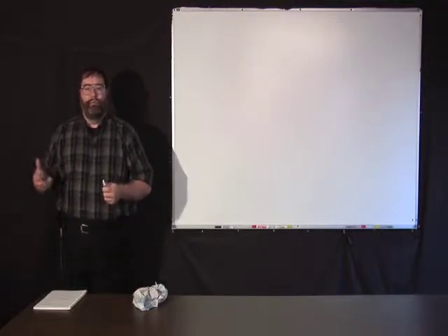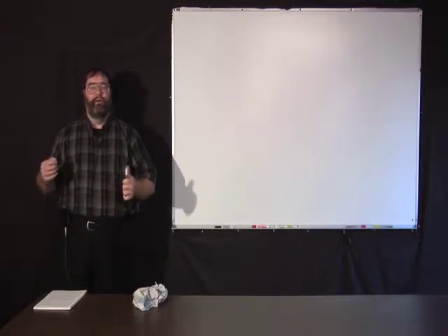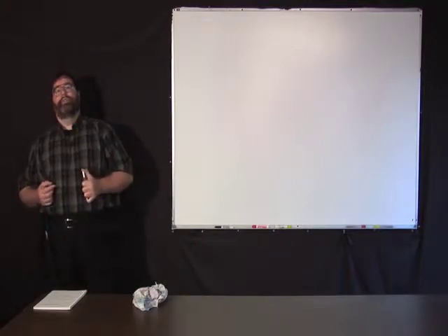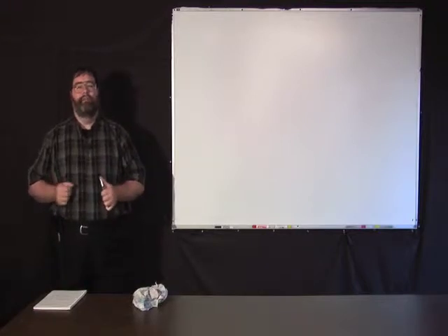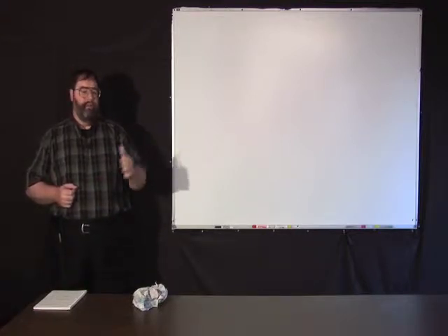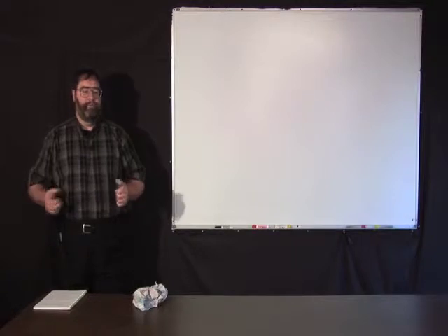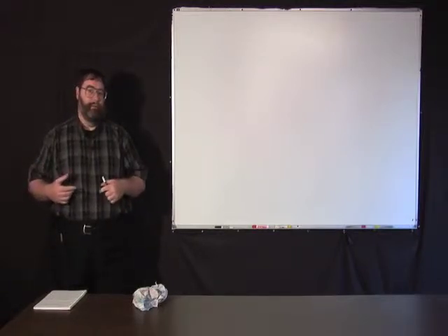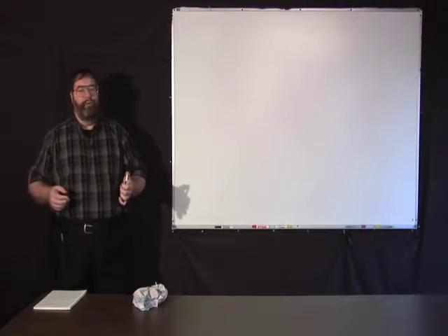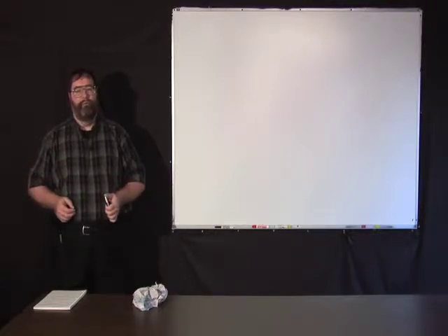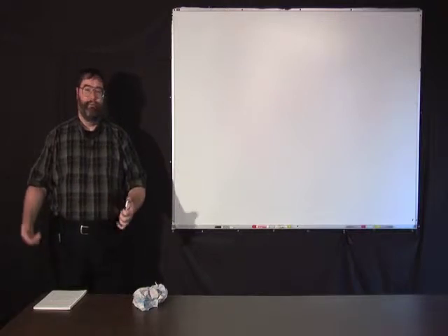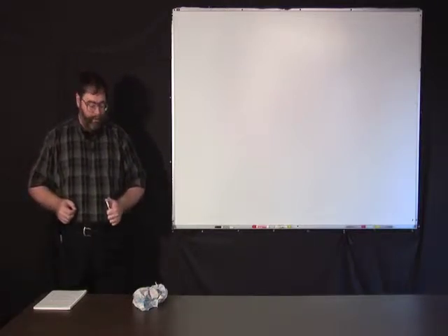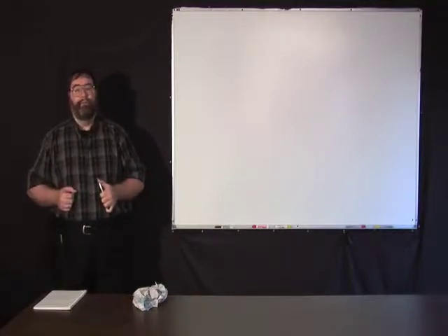You can call those fixed points, and that's what they're called in what's called the ITS-90 temperature scale. A series of temperatures were defined based on phase transitions of materials that determine a temperature scale. That temperature scale is close to being revised again, but right now, 1990 was the last time it was revised, with careful measurements and international agreement on what the temperatures of these fixed points are.